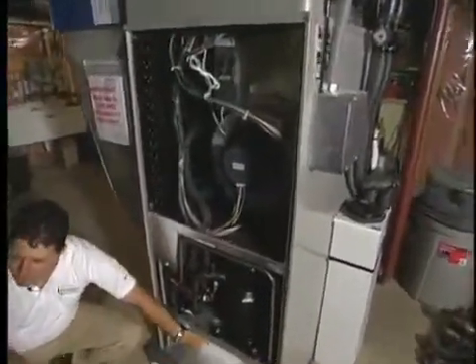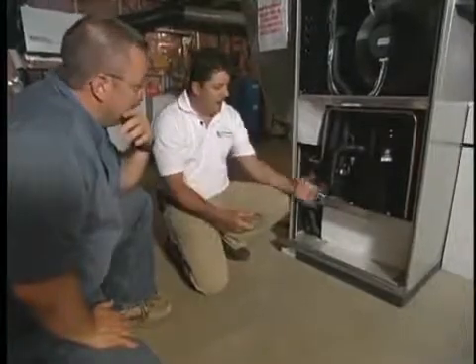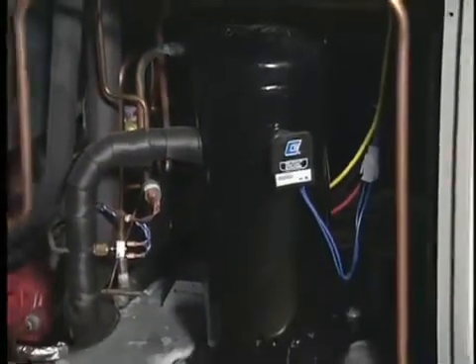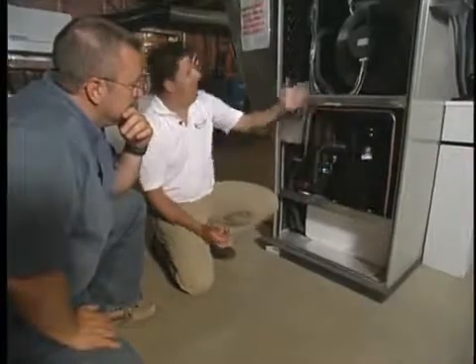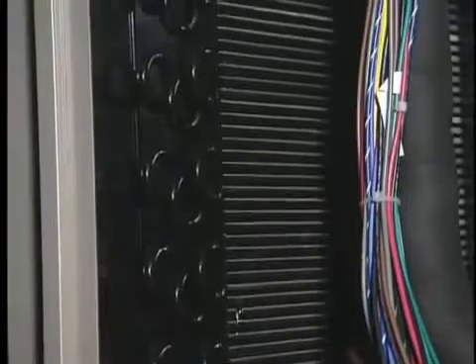So the water to refrigerant heat exchanger in the heating mode is absorbing heat energy from that fluid that's being circulated from the ground. And that's usually about 50 degrees, as we mentioned. Yeah, 50 degrees all the way down to 30 throughout the wintertime as we remove heat from the ground. And that energy then gets absorbed into the refrigeration system, and that's part of the compressor. So through that heat exchange process, we absorb the energy. The compressor then intensifies that energy through heat of compression. Of course, that's electric driven, okay? And once that energy is intensified, we take it to the second heat exchanger, which now we blow air across, which releases all that heat energy into the airstream, into the ductwork, and then obviously is heating the home.